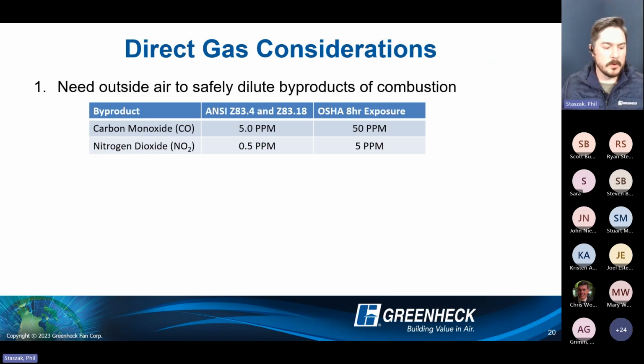And this is just to put it in real world terms and make everybody feel a little more comfortable. I know the shift away from gas, especially in the city of Seattle, but if we can still entertain it, this is just to have a conversation. Real world carbon monoxide levels: to put an ETL label on our direct gas fired equipment, we need to test to 5 parts per million of carbon monoxide and 0.5 parts per million of nitrogen dioxide.